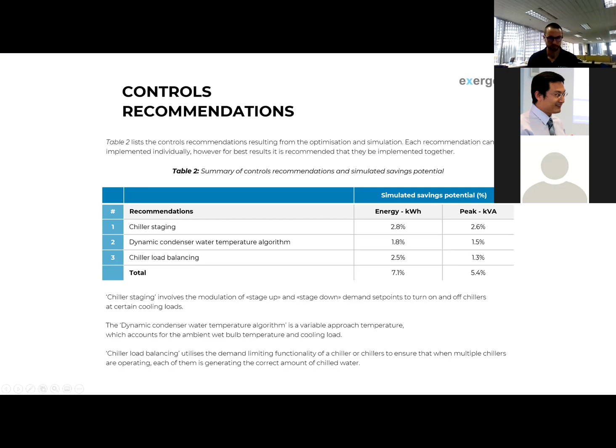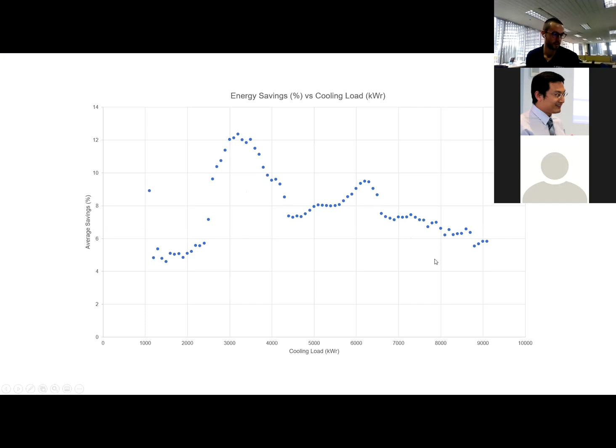So this is a graph that has come out of the simulation. On the x-axis here is the cooling load for the site, and then the average savings when we're comparing our optimized strategy with the existing control strategy. So it's not flat. There are different levels of savings at different cooling loads. Some of the graphs to come will show why that's the case, but you can see there's a definite hump around 3 to 4 megawatts of cooling capacity, and there's a specific reason why there was a really good potential for savings here, and still decent potential for savings elsewhere.